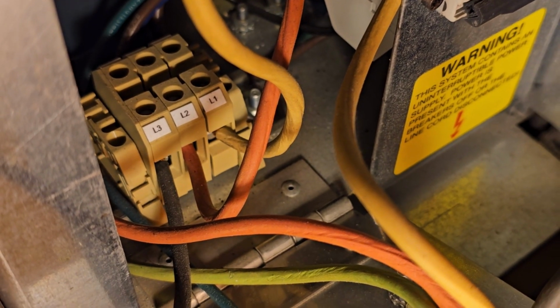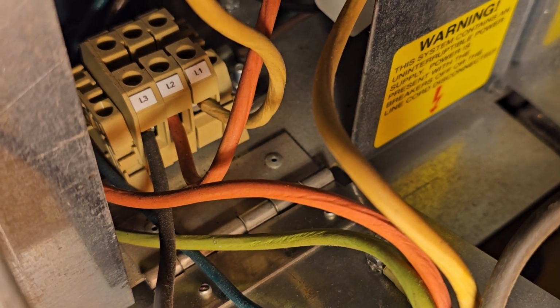Besides that, I'm going to reverse these two, the black and the white - I'll put the black back on L1 where it should have been, and the white on L3. Now I'm going to disconnect these 3 wires and get them out of the machine. After I change the connections in the transformer, I want to check this voltage here at this connector before it goes into the machine, so I don't cause any more damage. I don't want to have a problem.